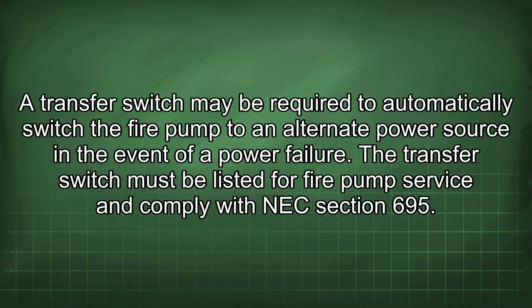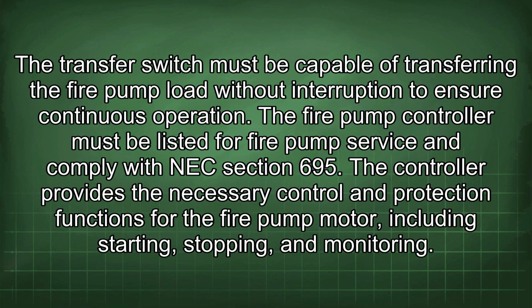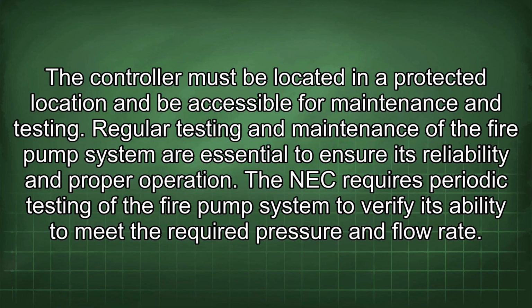A transfer switch may be required to automatically switch the fire pump to an alternate power source in the event of a power failure. The transfer switch must be listed for fire pump service and comply with NEC Section 695. The transfer switch must be capable of transferring the fire pump load without interruption to ensure continuous operation. The fire pump controller must be listed for fire pump service and comply with NEC Section 695. The controller provides the necessary control and protection functions for the fire pump motor, including starting, stopping, and monitoring. The controller must be located in a protected location and be accessible for maintenance and testing.